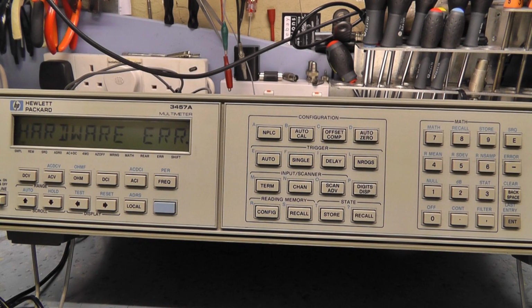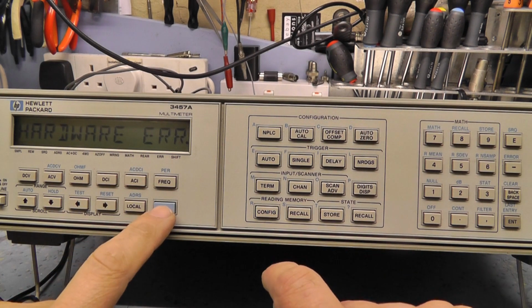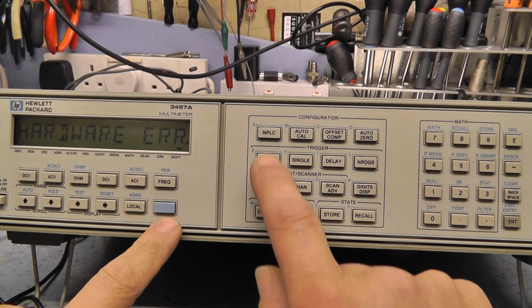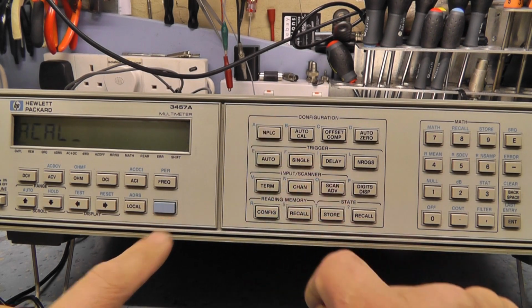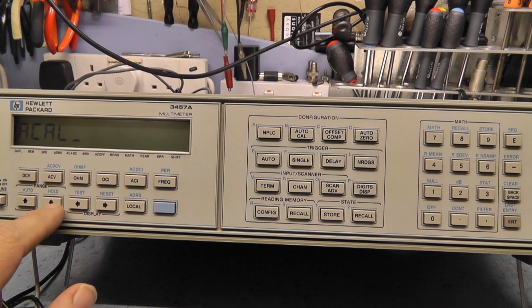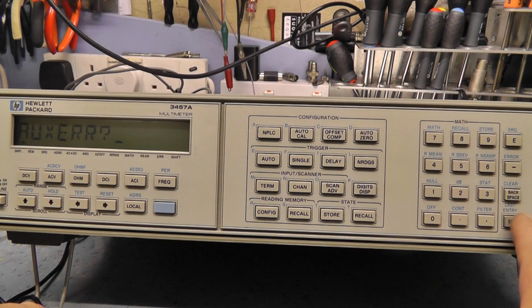It says if the message reads hardware error, check the auxiliary error message for additional information. Press the blue key and the number of power line cycles switch. We've got ACAL, and we scroll down to auxiliary error, press enter. And our auxiliary error, as you see there, is auxiliary error 256.